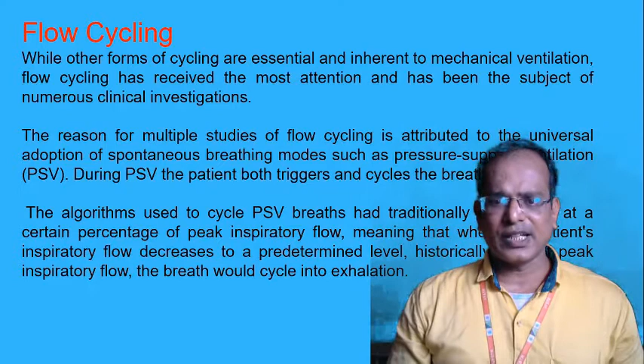We can see it in the graph. The algorithm used to cycle PSV breaths has traditionally been fixed at a certain percentage of the peak inspiratory flow, meaning that when the patient's inspiratory flow decreases to the predetermined level, historically 25% of peak inspiratory flow, the breath would cycle into exhalation.